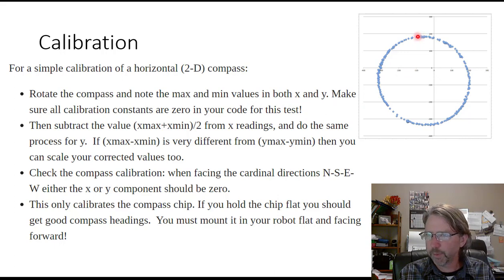So here are the y components. When the y is maximum, we should be facing north. When the x is maximum, we should be facing east, and west is the opposite. And then if we have the right center here, when we're facing north, the y is at a maximum and the x should be at 0. Up here, this should be x of 0. So those are the things to check. So we write down the maximum x's and the minimum x's and the maximum y's and the minimum y's as we spin around. You spin around several times, and you can have the code record the maximum. I'll show you that.